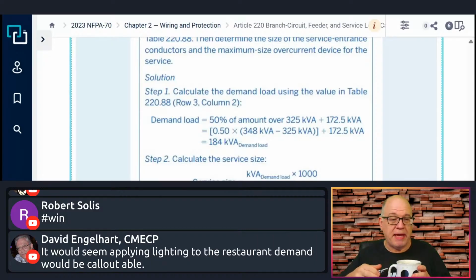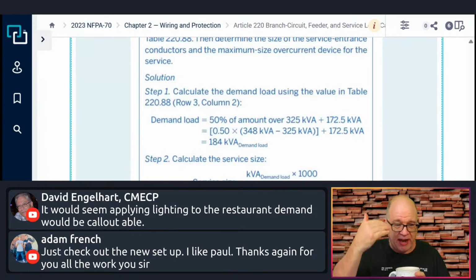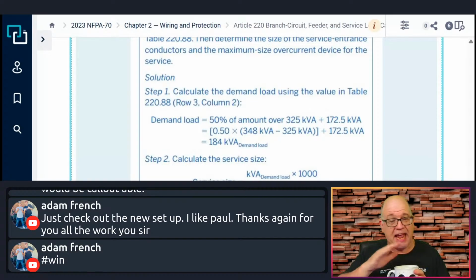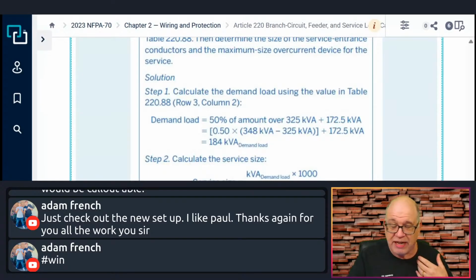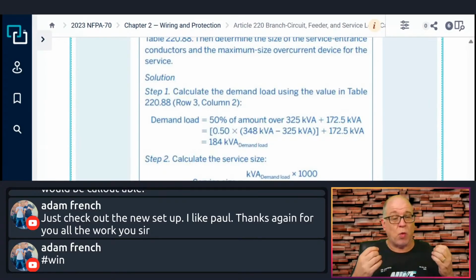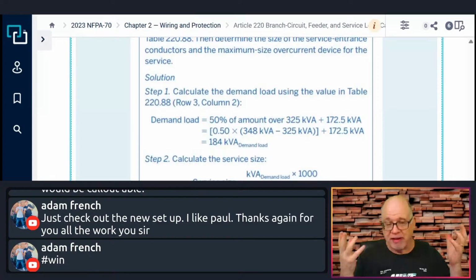Typically when I saw restaurants done under the optional method, they had already taken the actual output of the luminaires at their value, the wattage regardless of lamping. So they had a lighting schedule, and they took everything from it and added it in at 100%, not demanding anything. They added up the maximum wattage rating of the luminaire itself, not the lamping wattage, and added everything together.